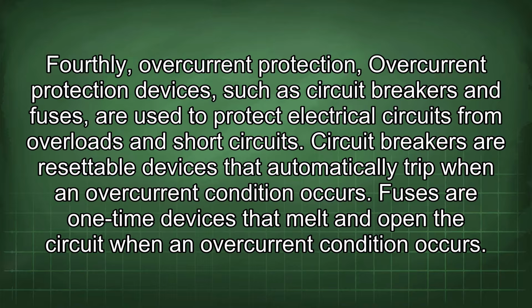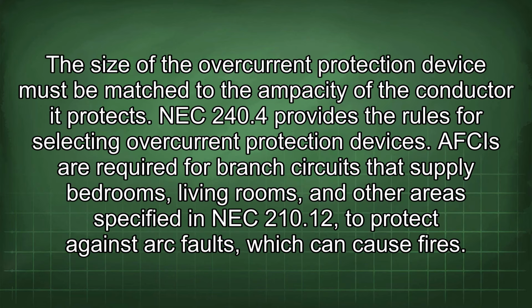Fourthly, overcurrent protection. Overcurrent protection devices, such as circuit breakers and fuses, are used to protect electrical circuits from overloads and short circuits. Circuit breakers are resettable devices that automatically trip when an overcurrent condition occurs. Fuses are one-time devices that melt and open the circuit when an overcurrent condition occurs. The size of the overcurrent protection device must be matched to the ampacity of the conductor it protects. NEC 240.4 provides the rules for selecting overcurrent protection devices.